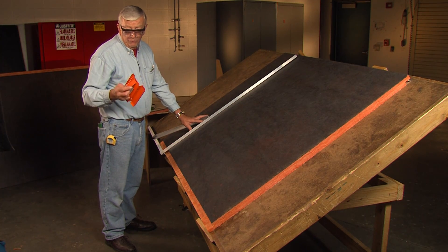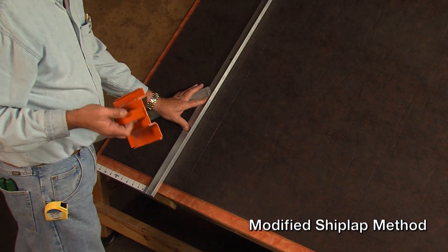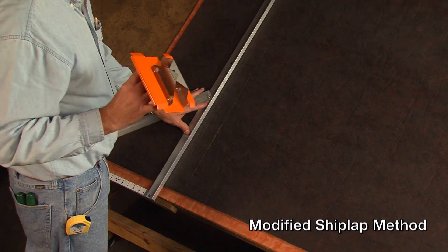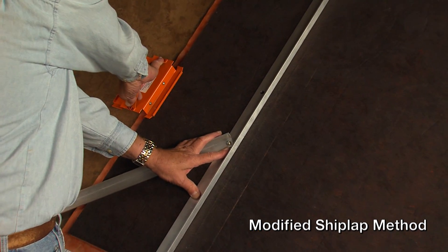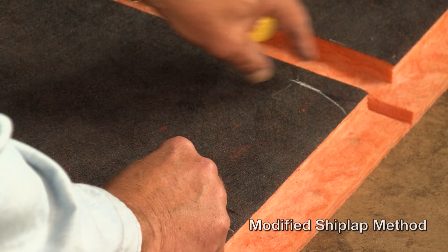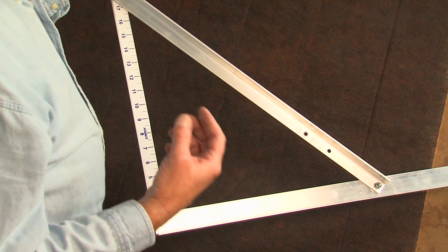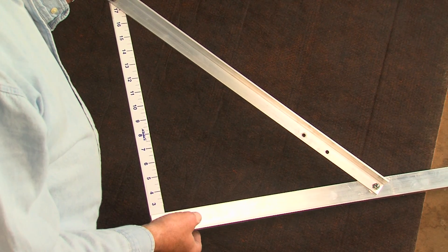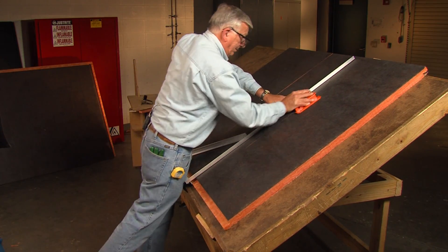There are times when knowing how to fabricate a duct from the flat comes in handy. The demonstrator will be using the modified shiplap tools from Amcraft. We recognize that some prefer to use the V-Groove method for hand fabrication. While this technique does not lend itself to fitting fabrication as well as the shiplap method, it is in common use. If you have V-Groove hand tools, the grooving sequence you are about to see is the same. NAIMA recommends the modified shiplap method for tighter side joints and stronger fittings.